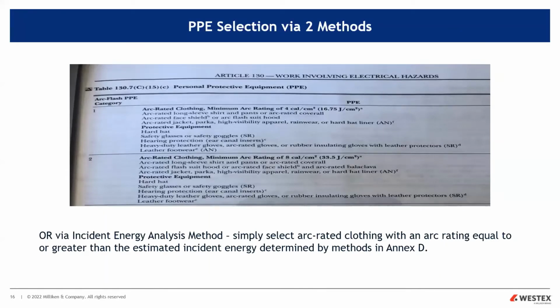Now, how do you select PPE? If you're doing the PPE category method, the third table you look at would be Table 130.7(C)(15)(c) for PPE. I just have arc flash categories 1 and 2 shown; of course, there are 3 and 4. I think most people are familiar: for category 1, the arc rating of the clothing or PPE has to be a minimum of 4 cal. For category 2, minimum 8; category 3, it's 25; category 4, the minimum PPE arc rating is 40. I think we're all familiar with that.